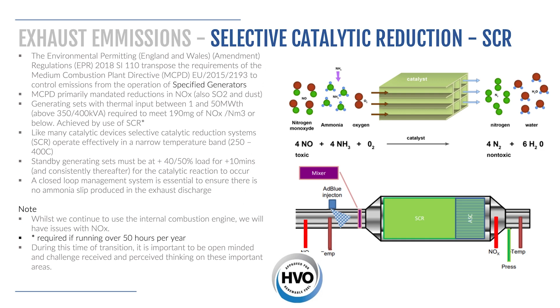It's important to note that the combining of burning HVO fuel and the use of selective catalytic reduction offers the best solution for all new installations. Whilst we continue to use the internal combustion engine, it should be noted that we will always have issues with nitrous oxide emissions. I mentioned just a moment ago about HVO. The standard diesel that we use in our road vehicles is the same as we use in a standby diesel generating set, and it's a product which is manufactured to BS EN 590 B7. It's known commonly as white diesel and contains a 7% bioelement.